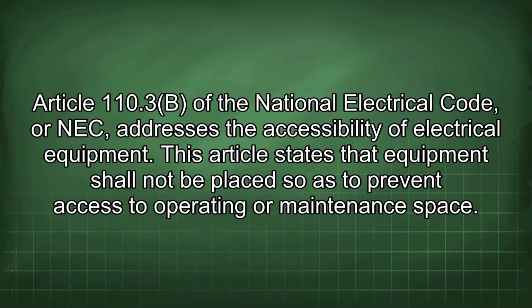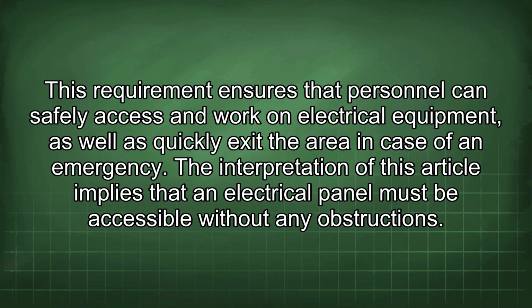Article 110.3b of the National Electrical Code, or NEC, addresses the accessibility of electrical equipment. This article states that equipment shall not be placed so as to prevent access to operating or maintenance space. This requirement ensures that personnel can safely access and work on electrical equipment, as well as quickly exit the area in case of an emergency.